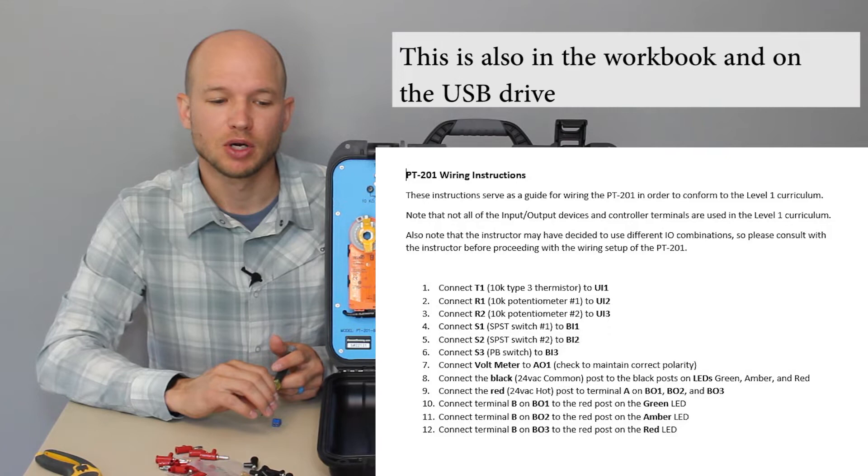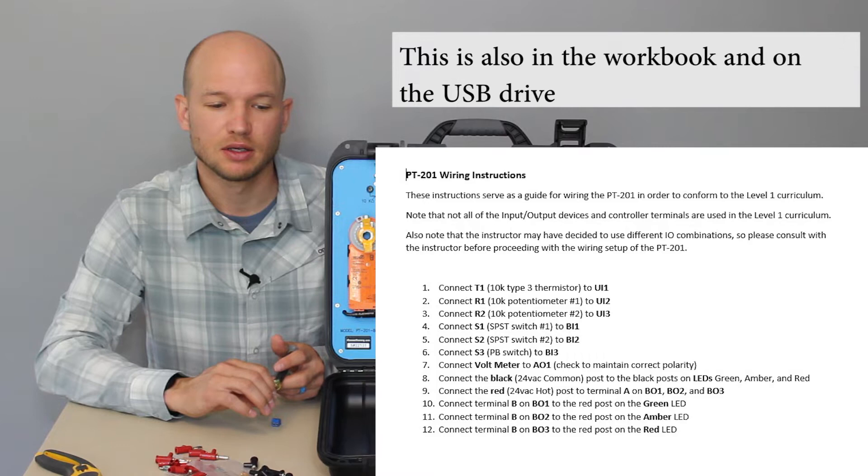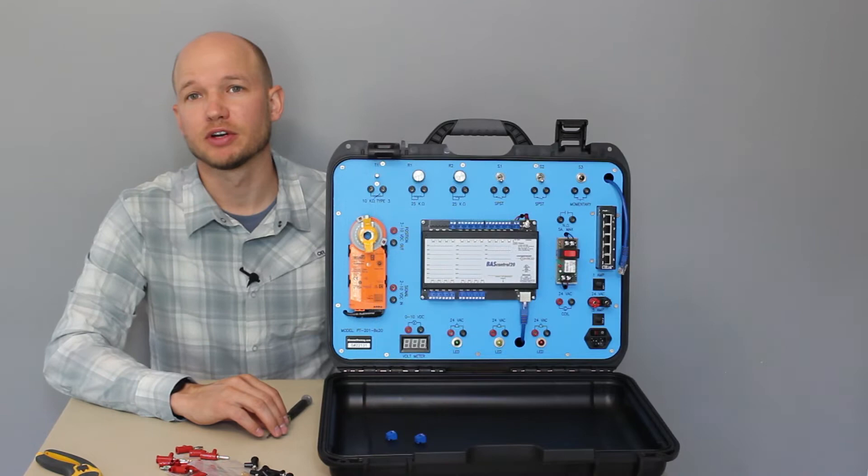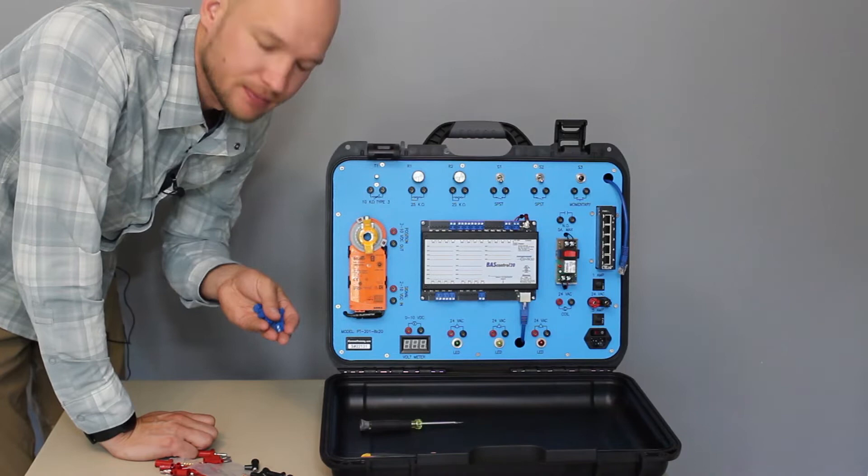So here you can see the point list. We're connecting T1 to universal input 1, R1 to universal input 2, R2 to universal input 3. You can see there's no universal input number 4 needed for curriculum 1. So we've pulled off all the connectors that we're going to use, and now let's get into the wiring.